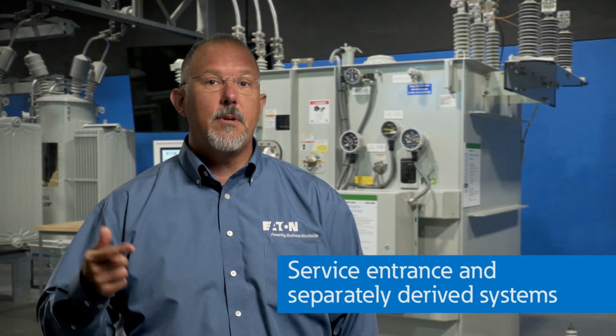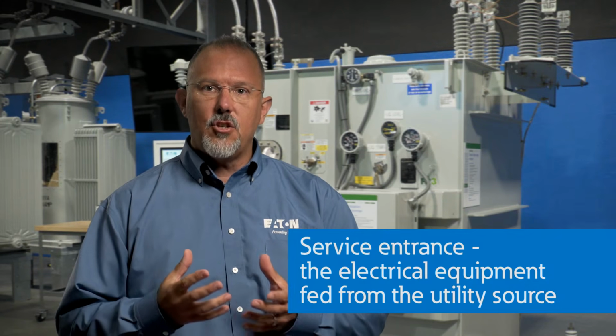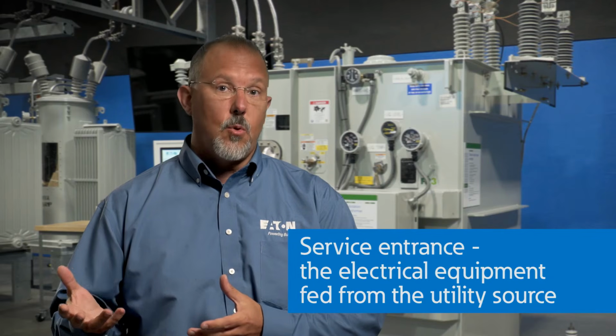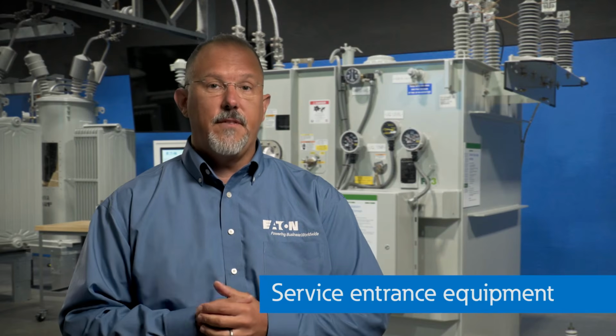For a larger electrical system, we have to consider many other things to properly ground and bond this electrical system. We will give a few examples of components and systems to hopefully clarify any confusion that may arise. Let's talk about two important terms, service entrance and separately derived systems. Simply put, think of service entrance as the electrical equipment fed from the utility source. This may include a transformer, a service disconnect, or other protective devices. There are very specific rules in the National Electrical Code for service entrance equipment and grounding.